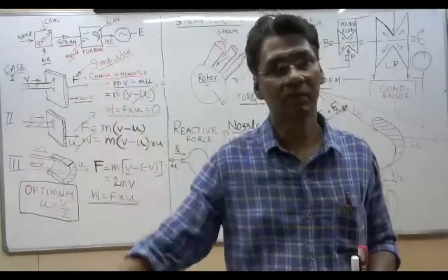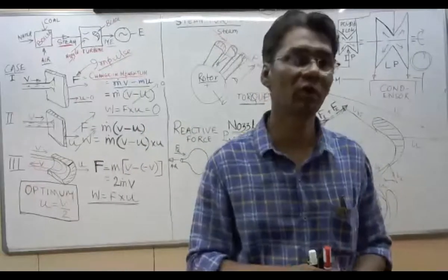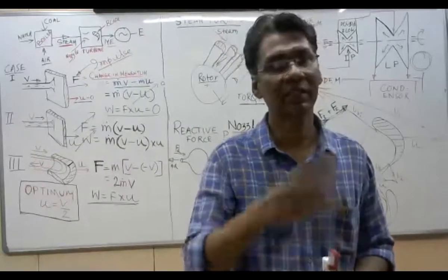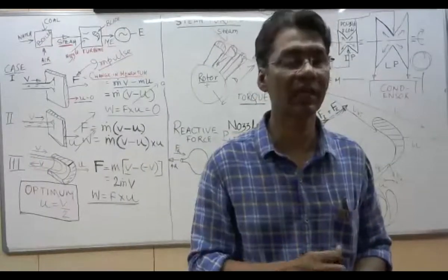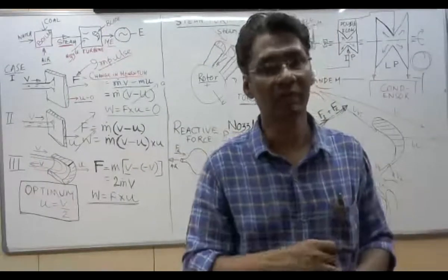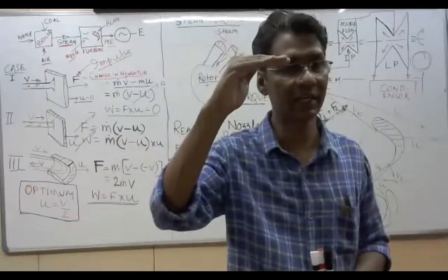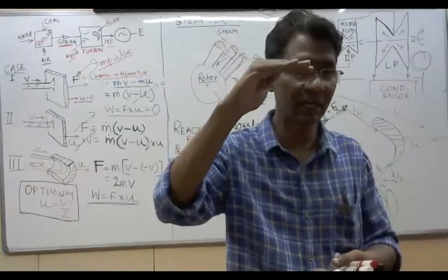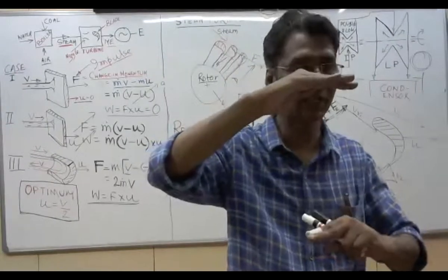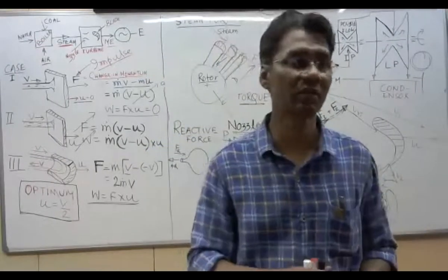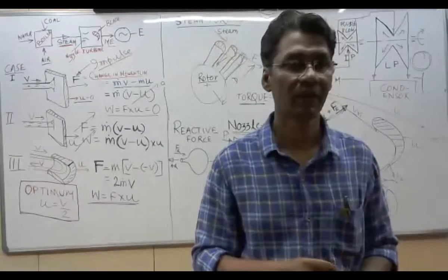At the condenser, the vacuum is below atmospheric pressure, that is, below 1 kg pressure. Condenser pressure is 0.1 kg, which is below atmospheric pressure. Atmospheric pressure is 1 kg standard, so 0.1 kg is the condenser pressure. That is the last stage pressure of the steam turbine.